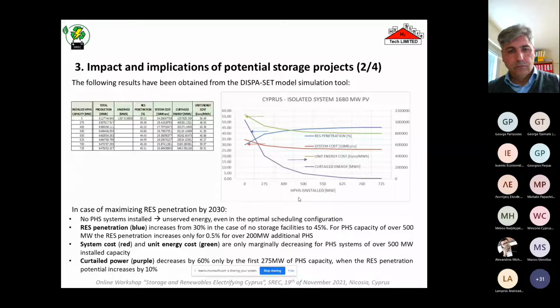Continuing with the results from the model simulations, the table on the left of the specific slide concentrates output parameters such as total energy production, unserved load, RES penetration achieved, curtailed energy, system cost, and unit energy cost in terms of euros per megawatt hour produced, for an installed hybrid storage capacity range from 0 to 725 megawatts. Zero installed capacity means that no pumped hydro storage system is installed. On the right side, there is also a graphical representation of the most crucial parameters with the hybrid storage installed capacity on the horizontal axis.